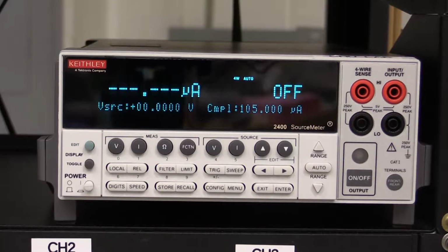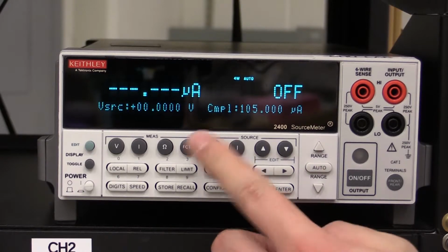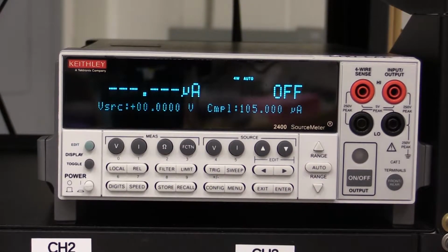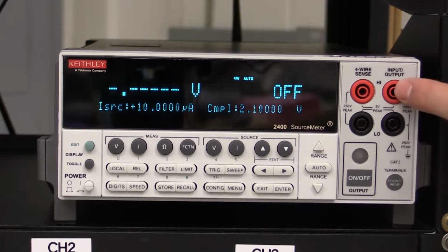So the Keithley 2400, or the 2400 as I'll refer to it from now on, is what's known as a source meter, which means it can source as well as sense current and voltage. You can configure this in a lot of different ways, but the two ways I'll configure it today are to source voltage and measure current, or conversely, you can source current and measure voltage. By default, the instrument will source as well as sense on these two terminals on the front right.